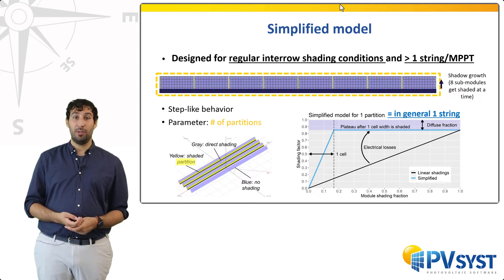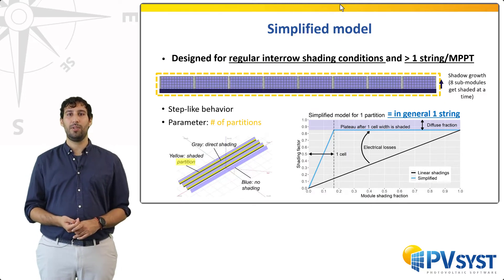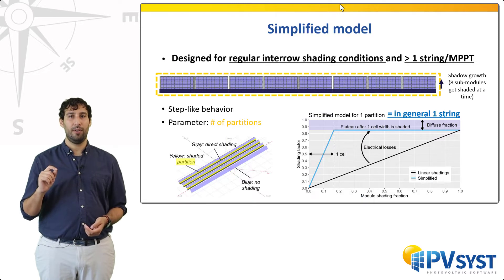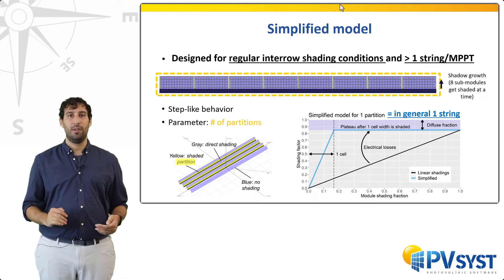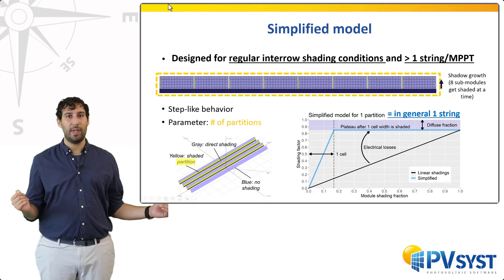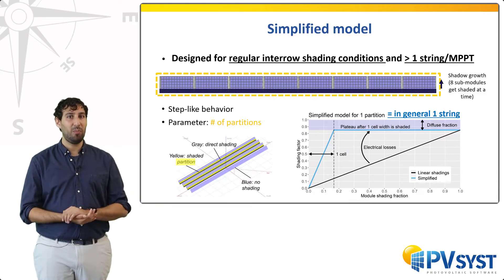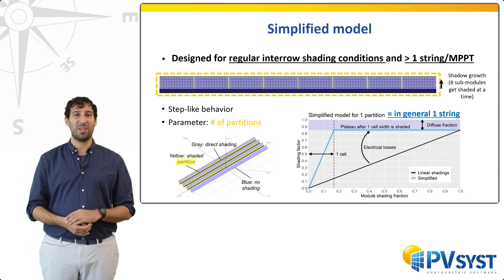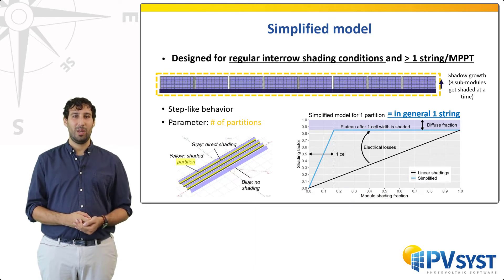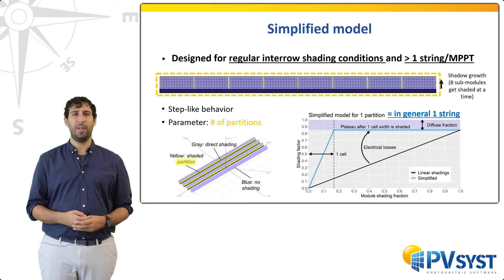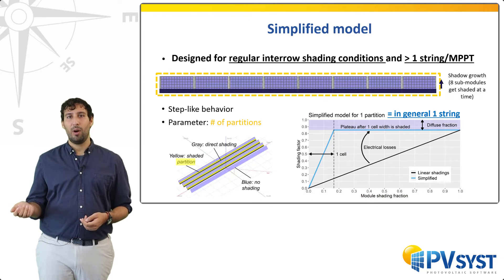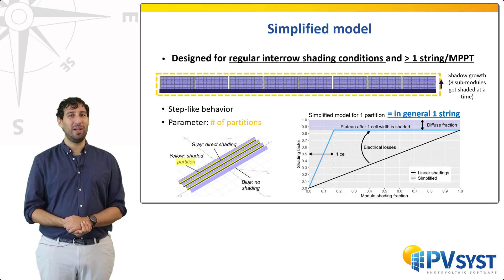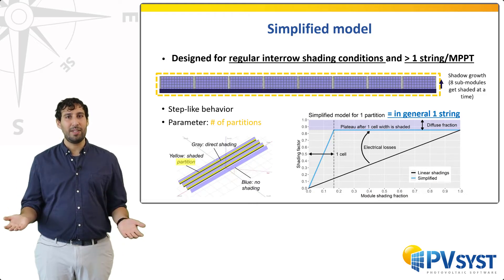In this situation, the mismatch between strings will cancel the contribution of the shaded string, as long as at least one cell within that string is shaded. This can be represented in the plot on the right. The x-axis describes the fraction of the total string height being shaded; the y-axis is the shading loss factor, equal to 1 when the production is 0. You can see that after one cell is covered, the shading loss factor is at its maximum. While this model was designed to be applied string by string, it can be extended to more general situations. The generalization is simple: instead of considering a string, one may consider a subdivision of a string — called a partition — and apply the same model. For example, in the case of a string of half-cut modules, one may apply the model over the lower half and then over the upper half.